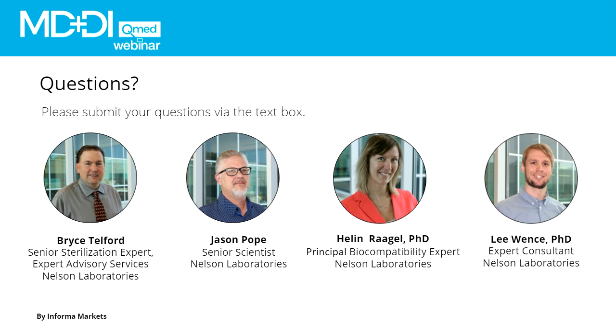So there is a variety of testing that we can do for the different packages. Also, it's going to depend on when and where the terminal sterilization is taking place, whether it's single use and distributed as sterile, or whether it's going to be point of use sterilization. So the answer is we do have various tests that we can do as part of a packaging / sterile barrier validation.